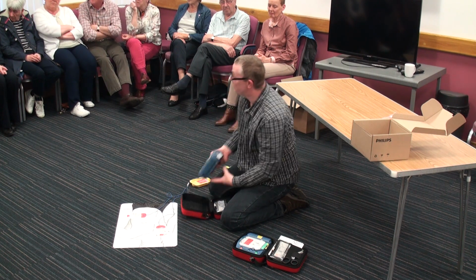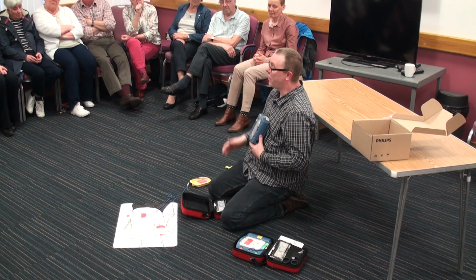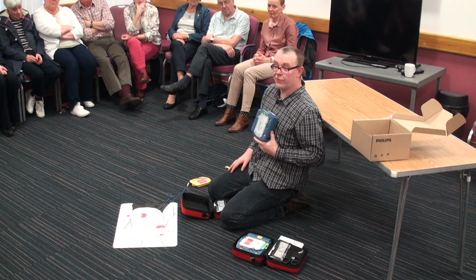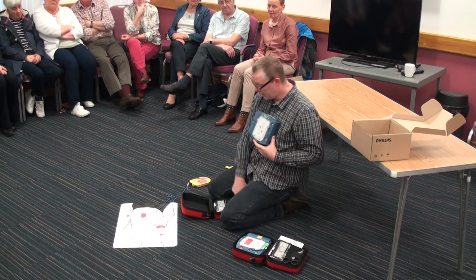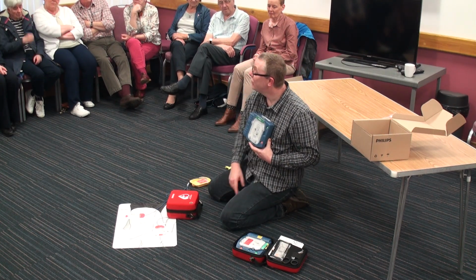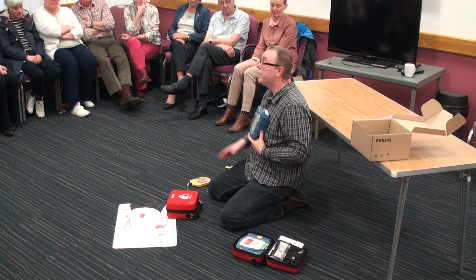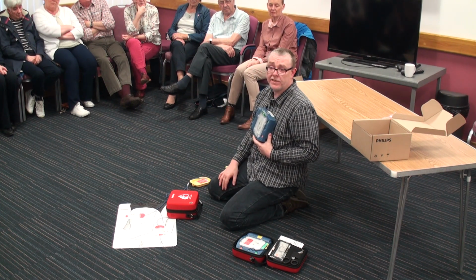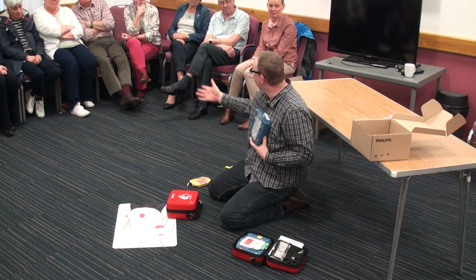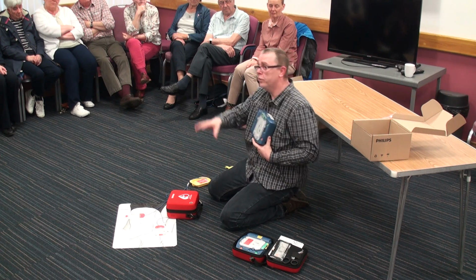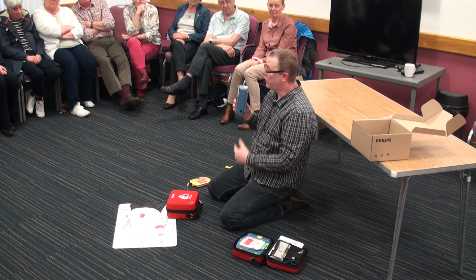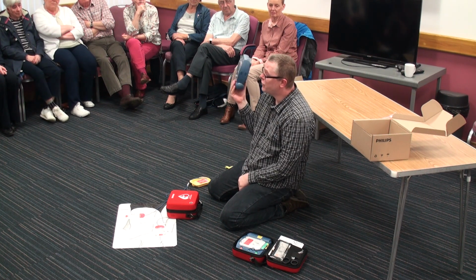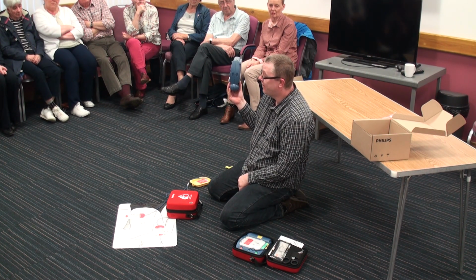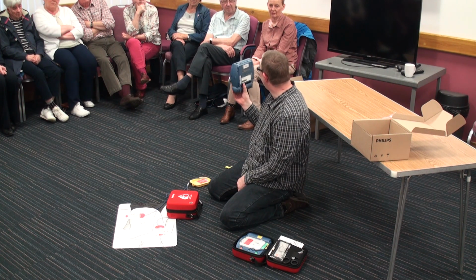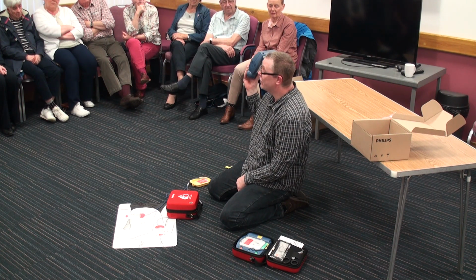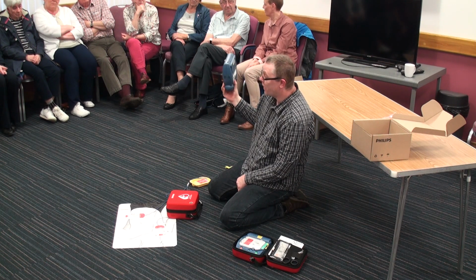This is your real machine. You see up at the top there's a wee green flashing light going off every 3 or 4 seconds - you can see that through the window of the case, so you don't need to open it. Every now and again, as part of your health and safety checks, whenever you're doing your fire extinguishers or first aid kits, just check the defib. The green light flashes, and these machines do 82 self-tests a month on themselves, checking everything from pad integrity to electronics to the battery.